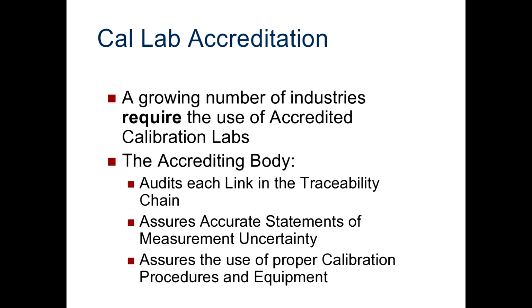The accrediting body audits each link in the traceability chain. They also assure that accurate statements of uncertainty are being presented, and they assure the use of proper calibration procedures and equipment. It's worth noting that the FDA themselves have become accredited in their own cal labs.